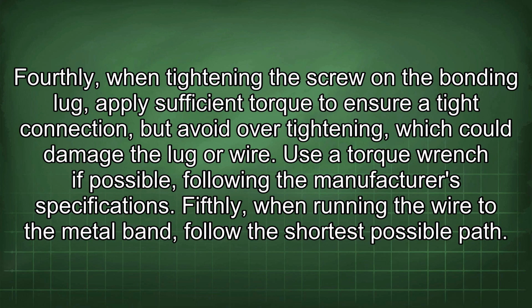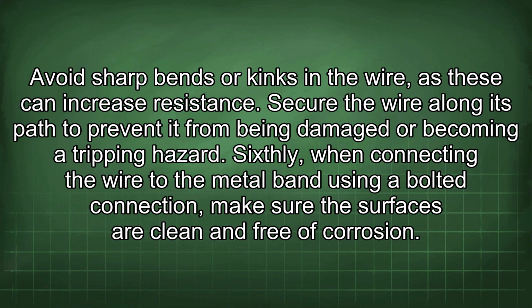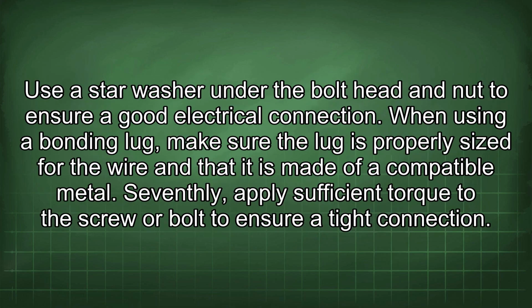Fifthly, when running the wire to the metal band, follow the shortest possible path. Avoid sharp bends or kinks in the wire, as these can increase resistance. Secure the wire along its path to prevent it from being damaged or becoming a tripping hazard. Sixthly, when connecting the wire to the metal band using a bolted connection, make sure the surfaces are clean and free of corrosion. Use a star washer under the bolt head and nut to ensure a good electrical connection. When using a bonding lug, make sure the lug is properly sized for the wire and that it is made of a compatible metal. Seventhly, apply sufficient torque to the screw or bolt to ensure a tight connection.